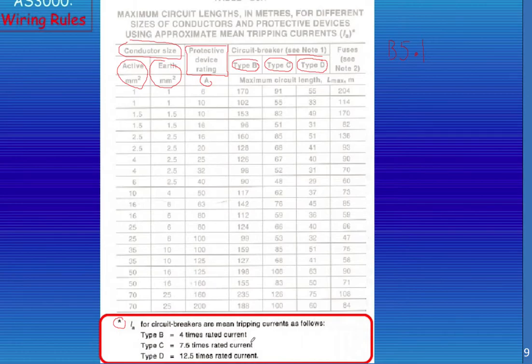And it's also telling us that for type B we have to allow four times rated current, for type C seven and a half, and for type D twelve and a half. And if you don't have circuit breakers but you have fuses, these are for standard HRC fuses.